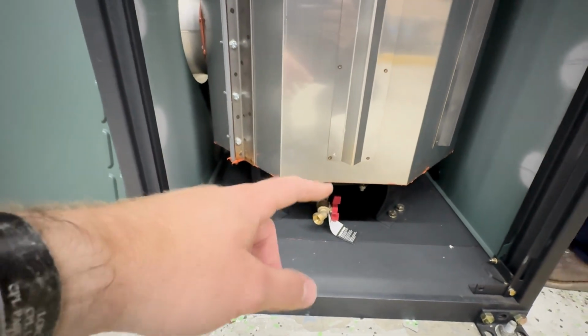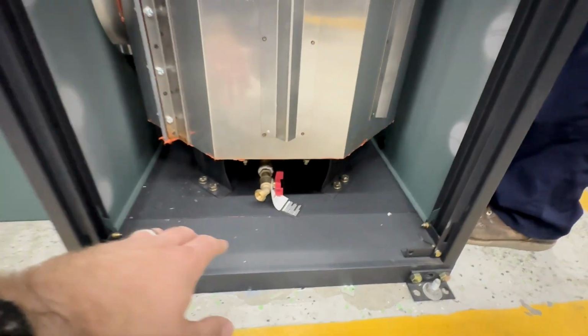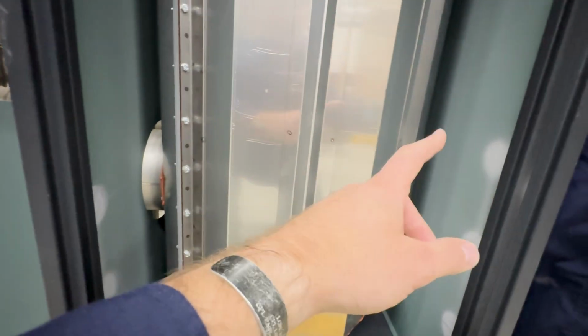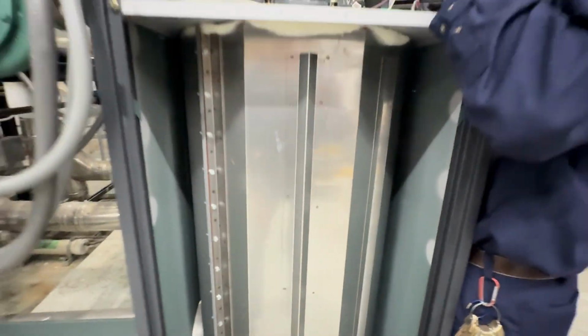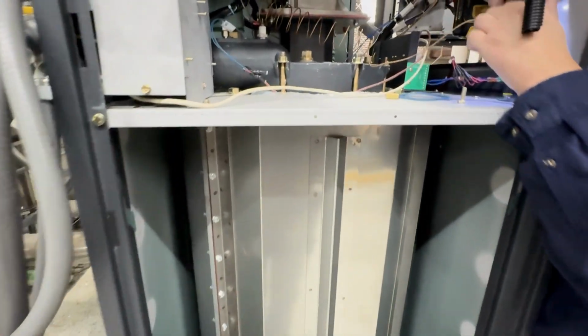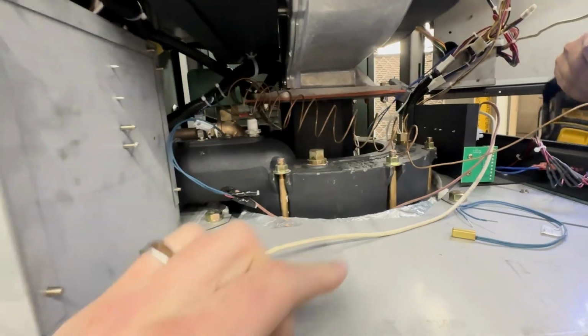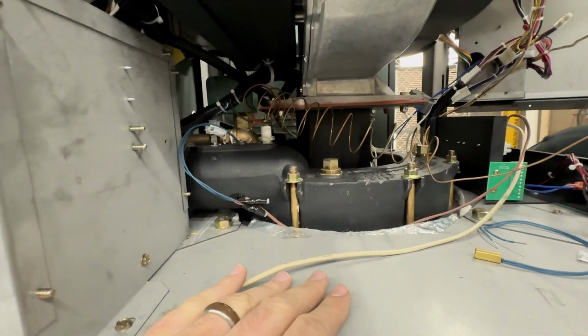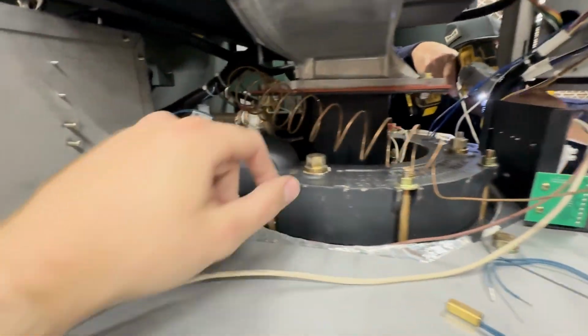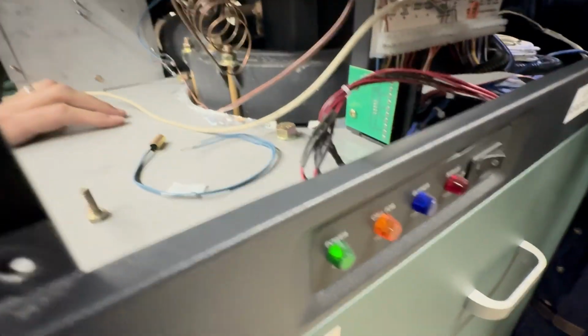We're going to check the gasket on this heat exchanger. We're going to look for any signs of water down here on the bottom, any heat scorching, anything outside of the boiler heat exchanger that could be an issue. Same thing, we're going to check up here in the control and the blower compartment. We're going to see if there's any scorched wires, make sure that all of our sensors are tight and not leaking, any signs of damage of any sort.